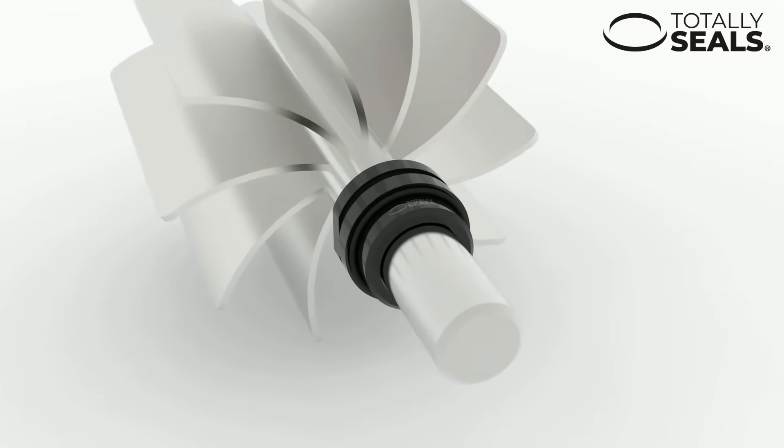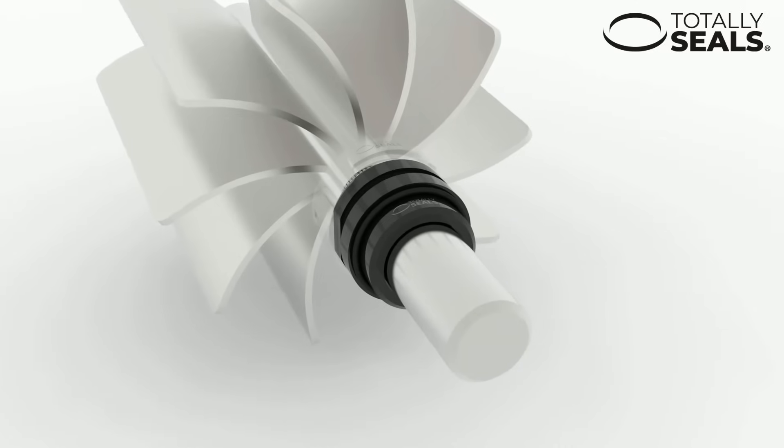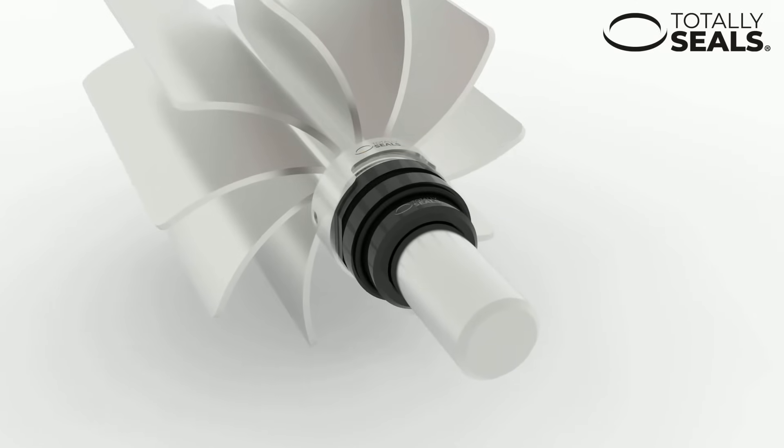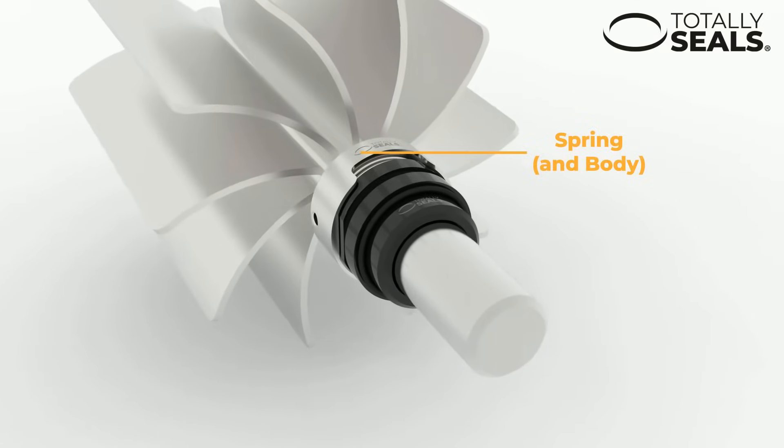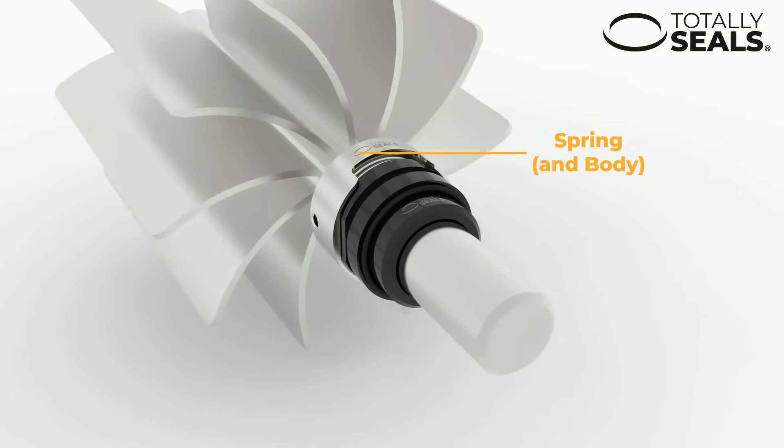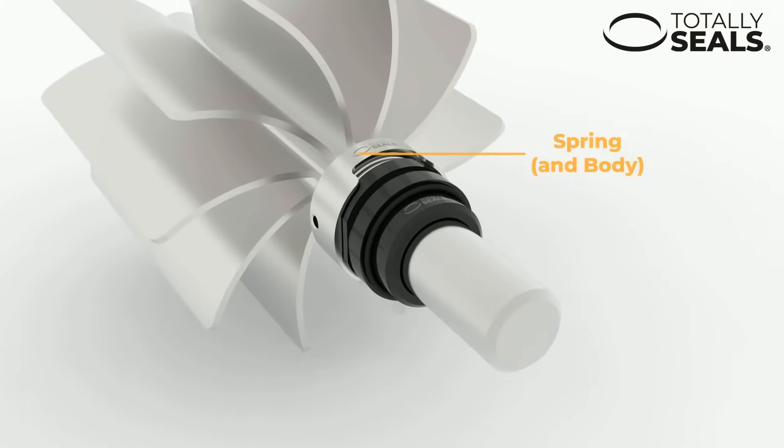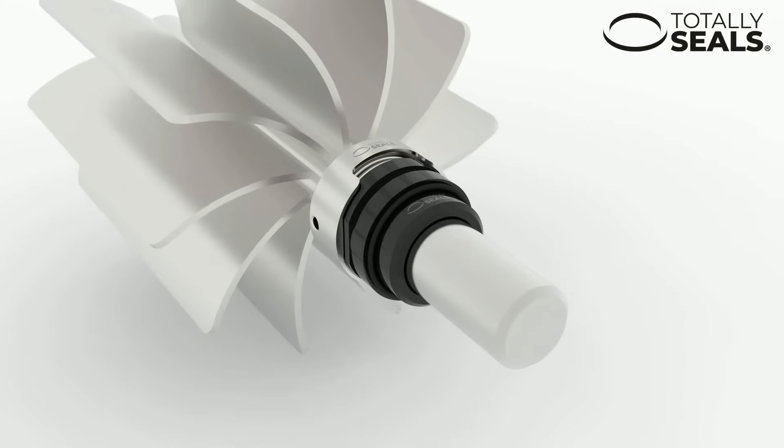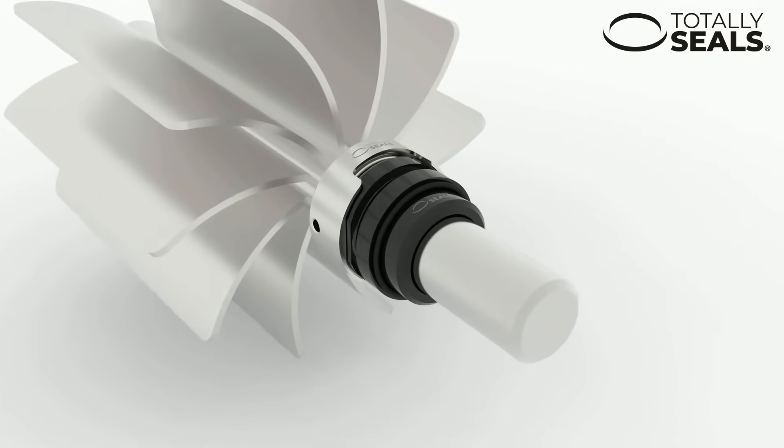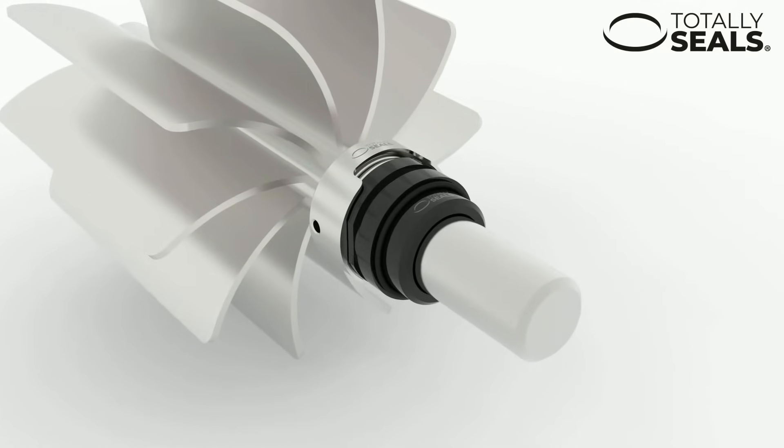And lastly a spring which is designed to keep the two sealing faces pushed together. This also self-adjusts the compression as the two seal faces slowly wear away.